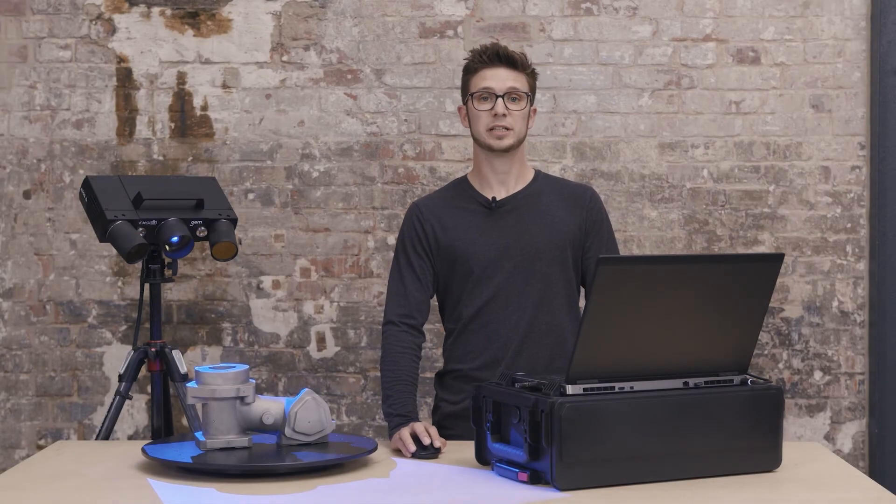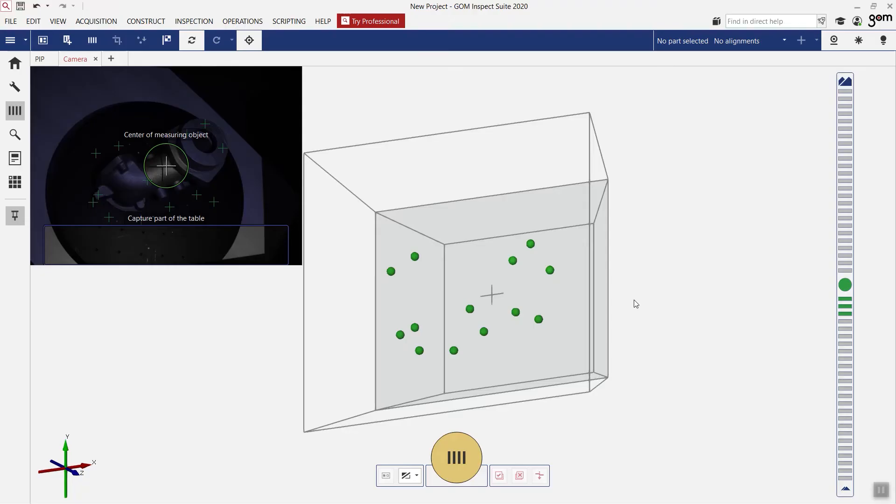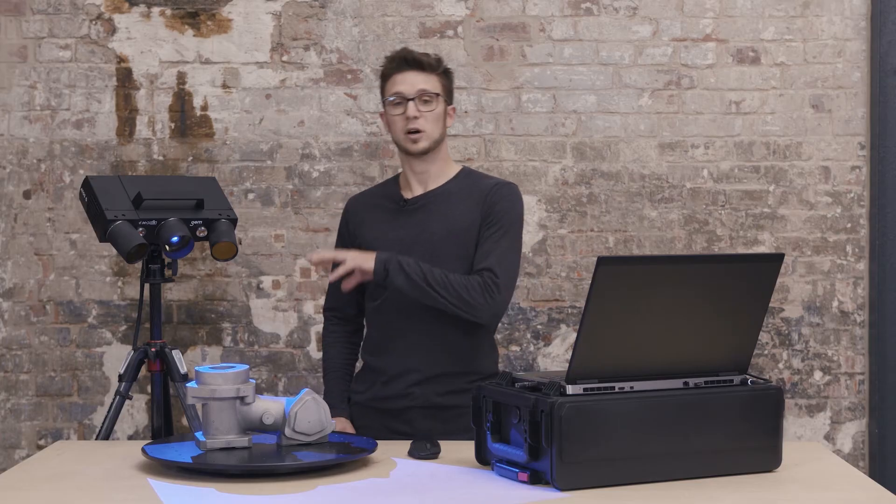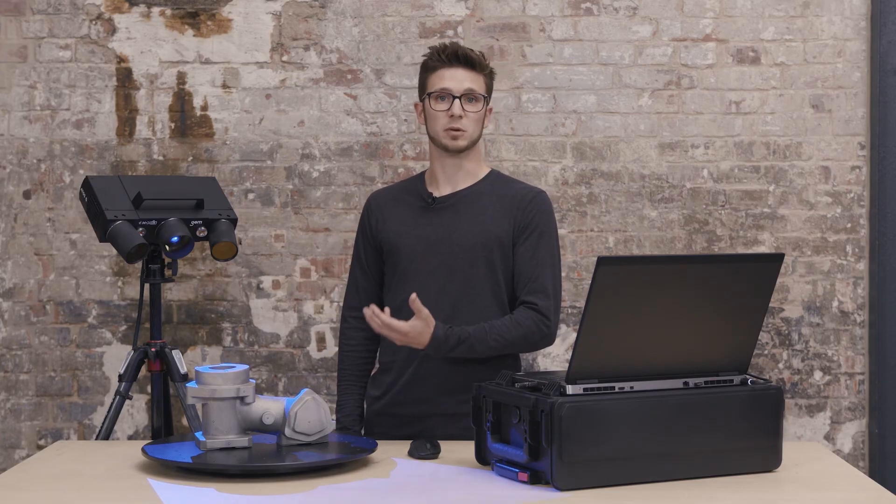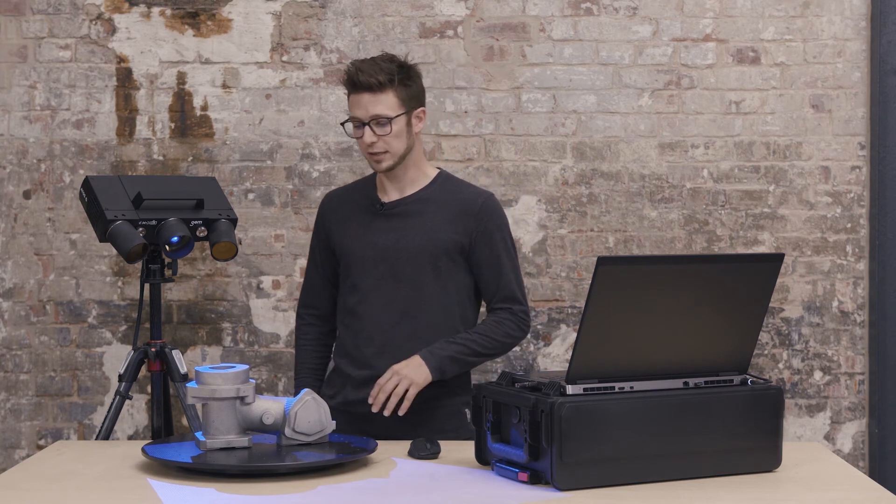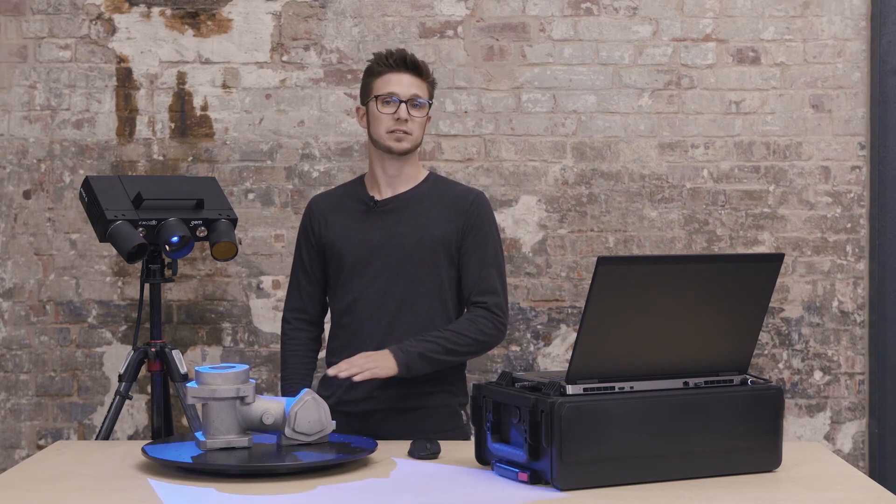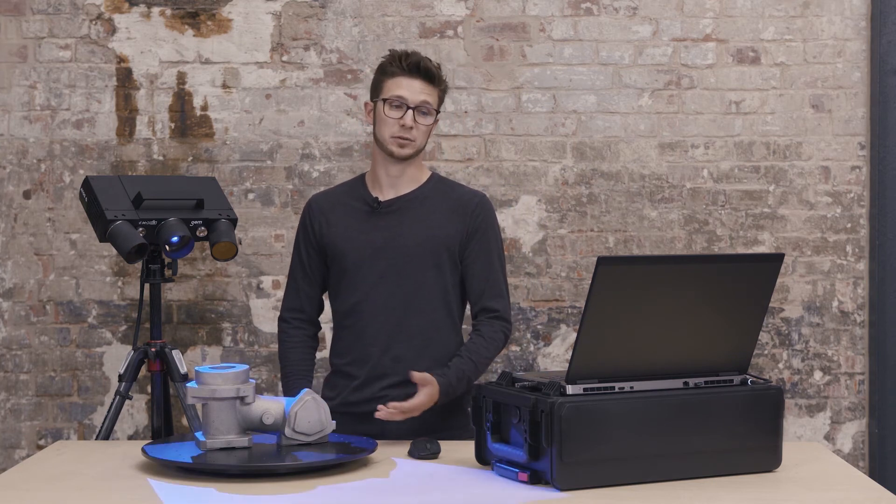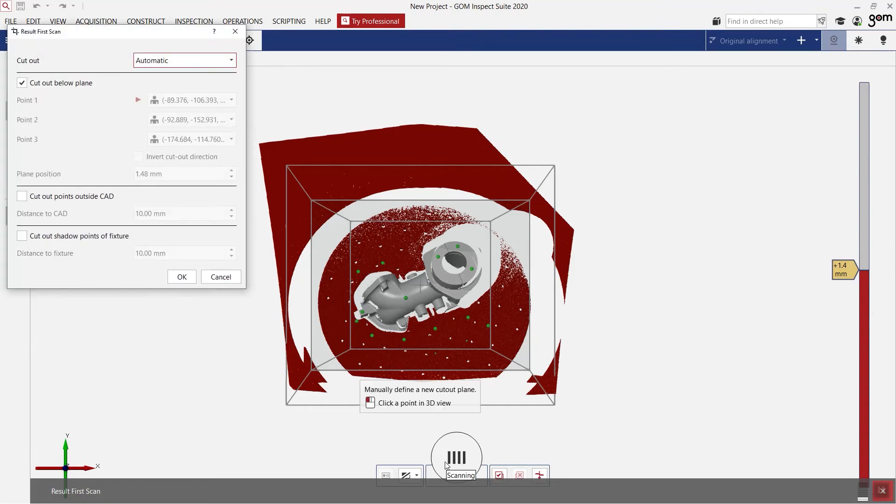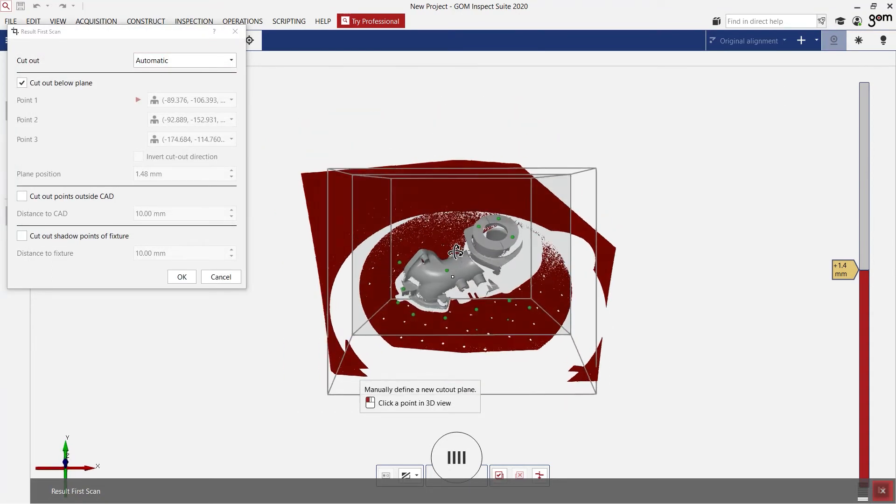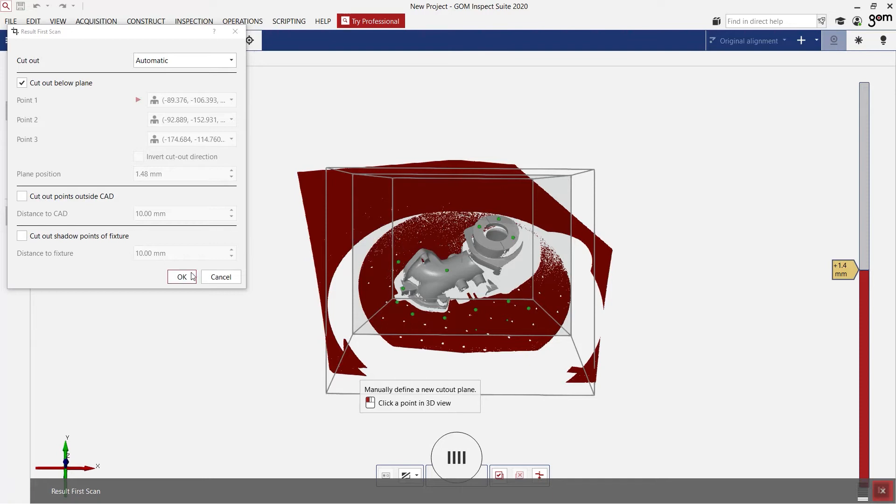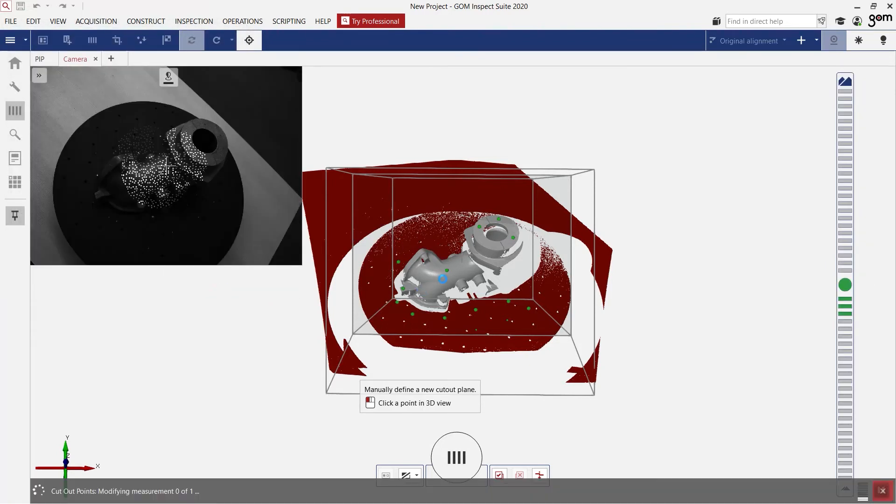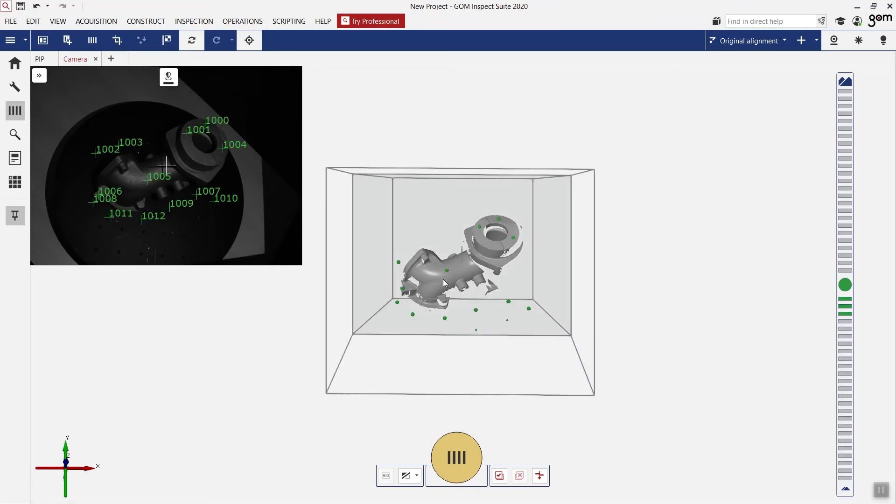Now we are ready to make our first scan. I can do that with the big yellow button below. The software automatically identifies which is the optimum exposure time to measure the part and will also automatically scan the table or the background. This result is shown here. We see that automatically everything that we don't need is cut away. So if I click on OK, I only have my part and I can continue scanning.